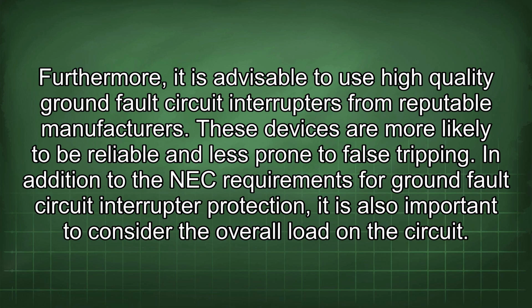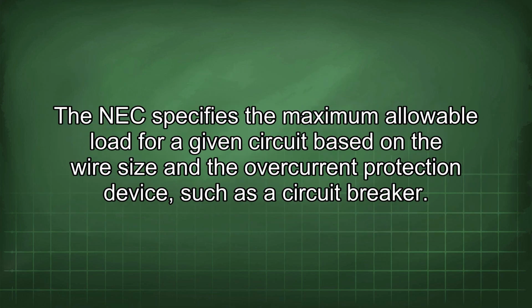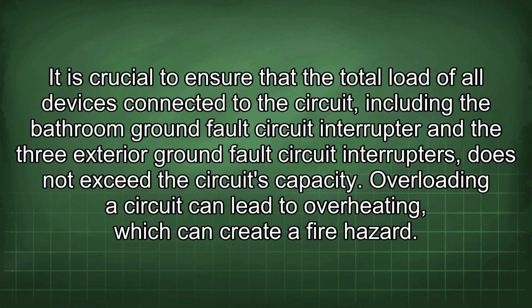In addition to the NEC requirements for ground fault circuit interrupter protection, it is also important to consider the overall load in the circuit. The NEC specifies the maximum allowable load for a given circuit based on the wire size and the overcurrent protection device, such as a circuit breaker. It is crucial to ensure that the total load of all devices connected to the circuit, including the bathroom ground fault circuit interrupter and the 3 exterior ground fault circuit interrupters, does not exceed the circuit's capacity. Overloading a circuit can lead to overheating, which can create a fire hazard.